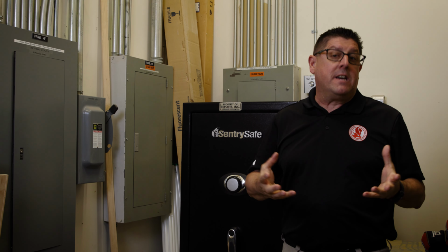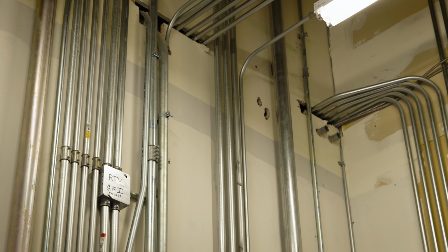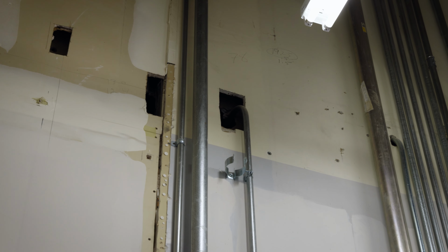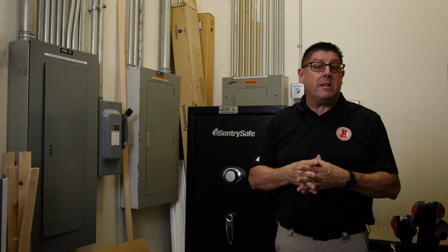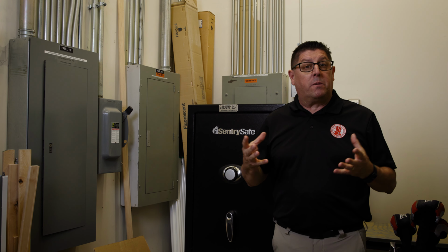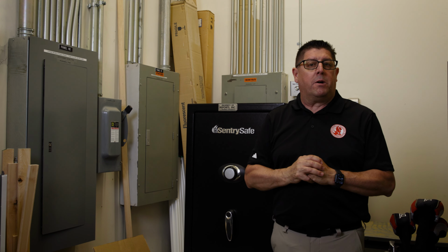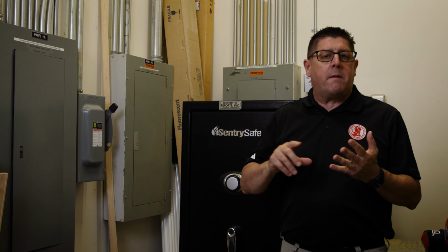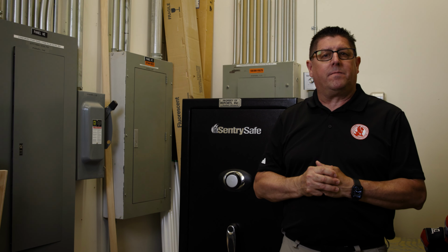And then lastly, as you go through your inspection, you're going to keep your eye open at partition walls. In this particular electric room, I have a large partition wall that separates this room from the rest of the building. And what I'm particularly looking for are penetrations. Penetrations like conduit or pipe penetrations or ductwork are all areas that if they penetrate these walls and don't have a proper seal, can transfer that heat or transfer that fire to another part of the building. And that's something we want to keep a mindful eye on as well. So think about storage and fire safety as you're doing your inspections.